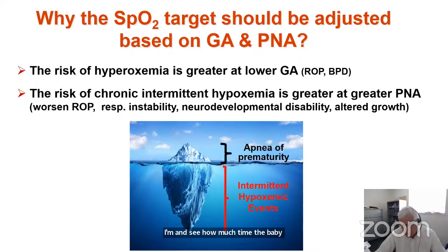However, the nurses fail to see all the chunk of ice that is under the water, which is significantly greater than the tip of the iceberg, and that is what represents the intermittent hypoxemic events. The only way to see this is by looking at the daily histogram and seeing how much time the baby is spending below the SpO2 targets.